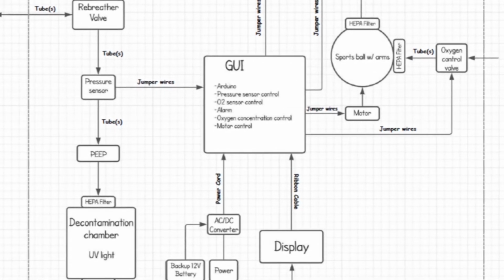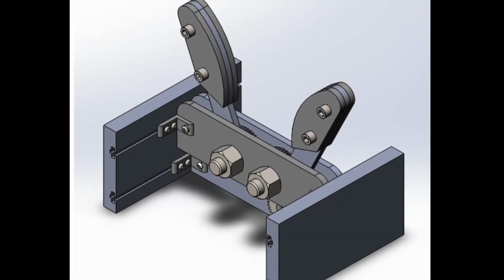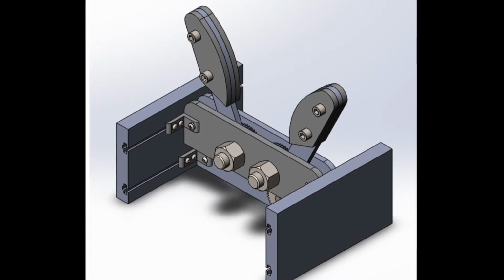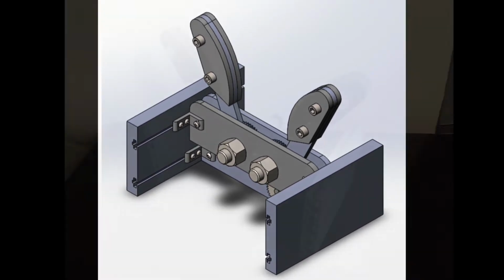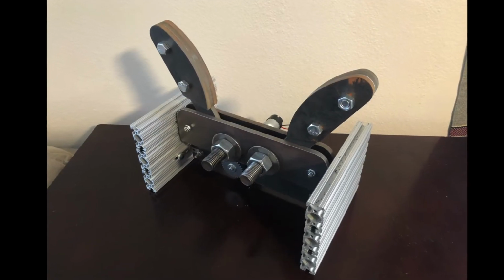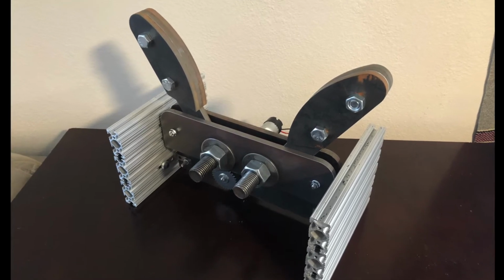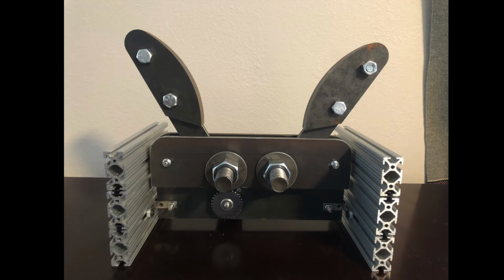The final mechanical design consists of a two-arm, gear-driven compression system that triggers the airflow from the air reservoir to the patient via the breathing circuit. Here's how it works. Two mechanical arms with an embedded gear are interlocked and supported by two plates and bolts. One of the arms is also interlocked with the pinion gear on the motor, the driving force of the mechanism.